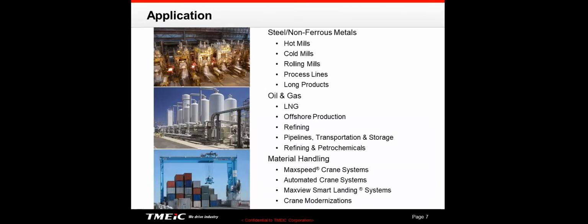So you can see there in that top picture, I was the director of engineering for a steel plant, the only integrated steel plant in the Western United States, Geneva Steel. And that's not a picture of Geneva Steel, but it looks somewhat like it. Now, we had a broadside mill that was 50,000 horsepower. And then it went through 6 finishing stands that hit about 12,000 horsepower. The peak torques were extremely high as compared to the average torques.